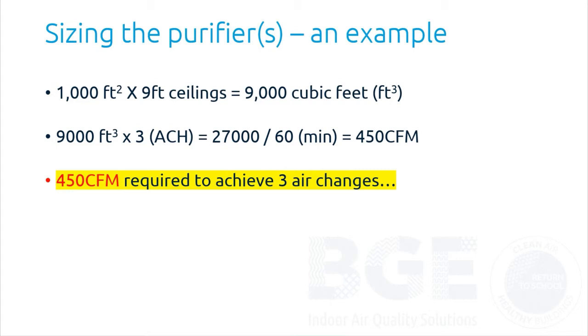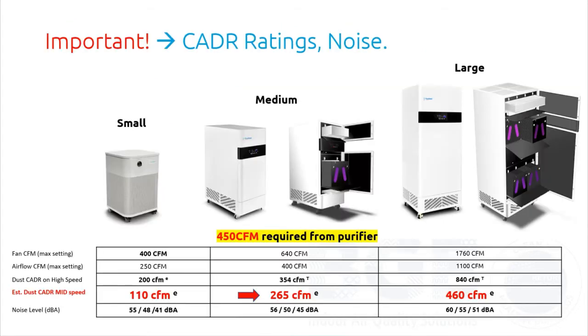Now we know what we need, we know what we're getting. Now, how do we pick one? In this example, we're looking for about 450 CFM. There are a few things you could do here. You could go right to the big one and you would be at the right amount for the CADR. Now, in this example, we've adjusted for noise levels. In a classroom, if it's quiet and you're trying to teach, you're probably not going to run these on the highest level just due to sound. So we've adjusted this down to the medium level. If you can run them at high, you could use less, but realistically, you're going to use the second level. So you can get the big one, which will run at about 460 on medium.